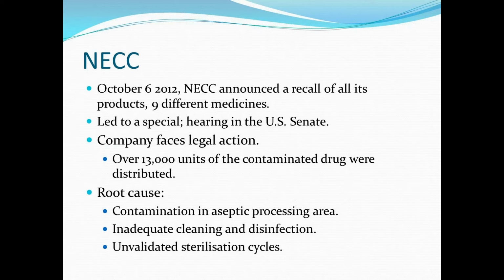The root causes were contamination in the aseptic processing area. So when state pharmacists and the FDA went in, they found mold on the HVAC grills leading into the clean room.